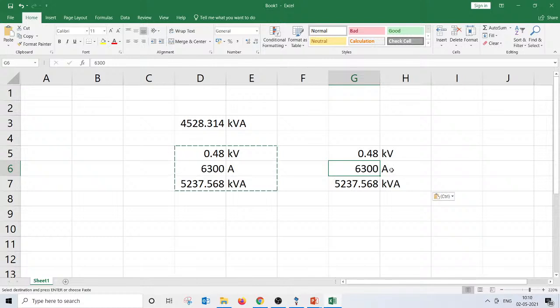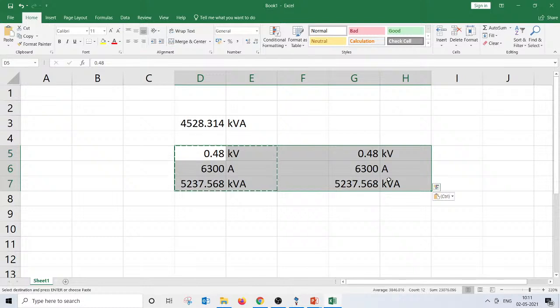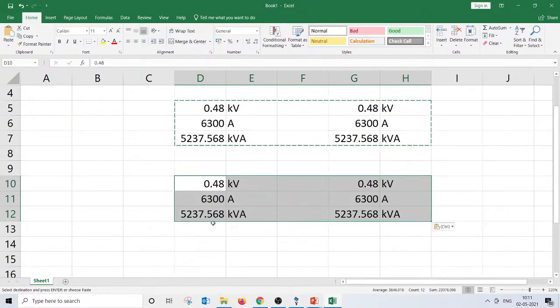And 6300 amps, shall I load up to 6300 amps? Yes, you can load. But if we have a transformer of 5.25 MVA, is the LV side voltage fluctuation zero? The answer may not be. So what's the voltage fluctuation which is allowed? Maybe 10%. So when I go with a 5.25 MVA transformer, the current will be 6300 at 480 volt. But because of whatever the voltage fluctuation in the grid, or because of the heavy load, if the 480 volt side voltage comes down, do you think the current remains the same? The answer is no. So what I am trying to mean by that is, this is theoretically okay, but you need to always account for the voltage fluctuation in this.